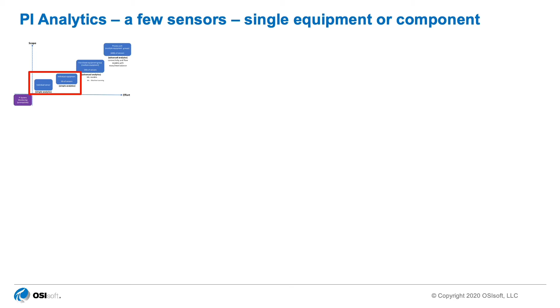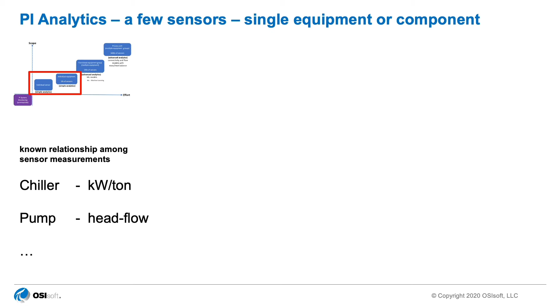Typically this is what we have done. Like on a chiller, I typically use kilowatt per ton as a metric. I get the BTUs that the chiller is putting out, and I know the kilowatt consumption, so it is a simple calculation for me to do a kilowatt per ton. Or on a pump, instead of individually looking at the pressure and the flow, I do a combined head flow calculation and use that as a metric. And this doesn't have to be just bivariate. You can apply it even at a system level. So that is really the next level of complication, the next rung of the ladder. But basically, the head flow and the kilowatt per ton usage is the manifestation of it.